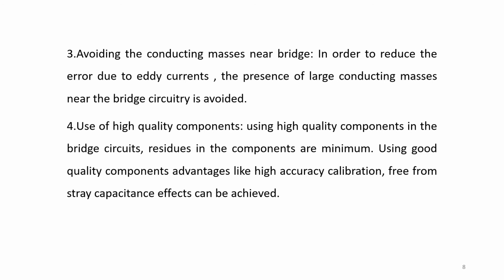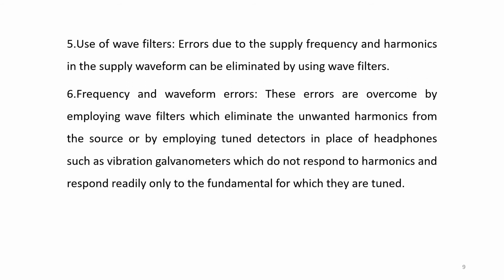So, avoiding the conducting masses near the bridge. In order to reduce the errors due to eddy currents, the presence of large conducting masses near the bridge circuitry must be avoided. Next, the use of high quality components. Using high quality components in the bridge circuits, residuals in the components are minimum. So using good quality components, advantages like high accuracy calibration and freedom from stray capacitance effects can be achieved. Next is the use of the wave filters.